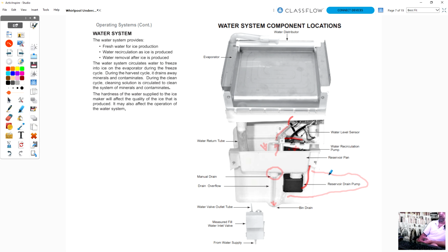That is what's telling the board if you have enough water in there. One of the biggest problems we have with these ice machines is that over a period of time they run out of water in the circulation pump, and you'll hear the pump sucking air, and it's not circulating water over the evaporator. On the older ones, it was usually either low water pressure to the customer's home or a bad water valve. So if you're running into a customer saying poor or slow or no ice production, and you're hearing that circulation pump laboring or sucking air, most likely it's your water valve problem here.